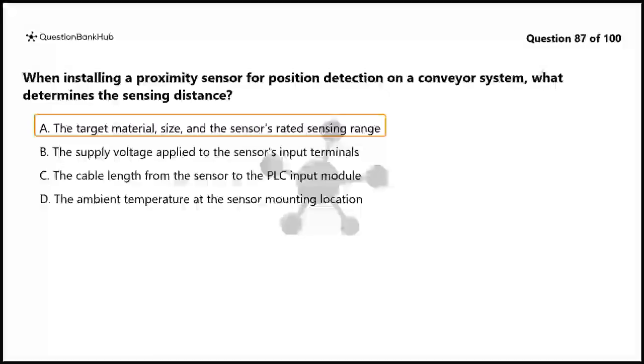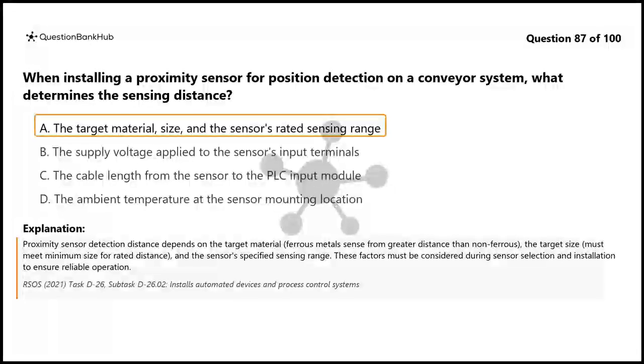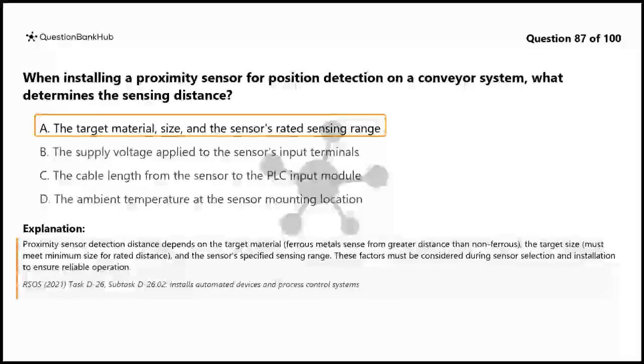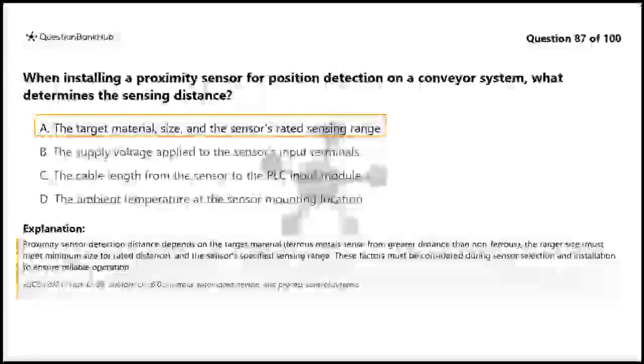The correct answer is A. The target material, size, and the sensor's rated sensing range. Proximity sensor detection distance depends on the target material. Ferrous metals sense from greater distance than non-ferrous. The target size must meet the minimum size for the rated distance, and the sensor's specified sensing range applies. These factors must be considered during sensor selection and installation to ensure reliable operation.